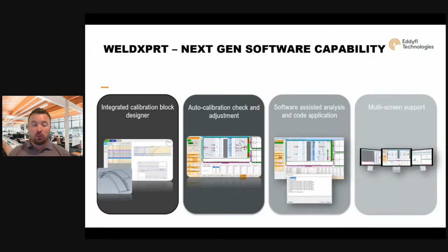So the ability to do automatic calibration checks. With these, because the software knows the position of the reflectors, their orientation, sensitivity, we can automatically check the calibration block to check that all of those channels, which are each targeting individual zones, are properly tuned and properly sensitive to the indications they're supposed to find. So it's looking for the correct position, sensitivity, and time of flight for each one of those channels. If they're all good, it gives us a green cal success button. If something is wrong, one or more of those reflectors is out, we get a red calibration failure.